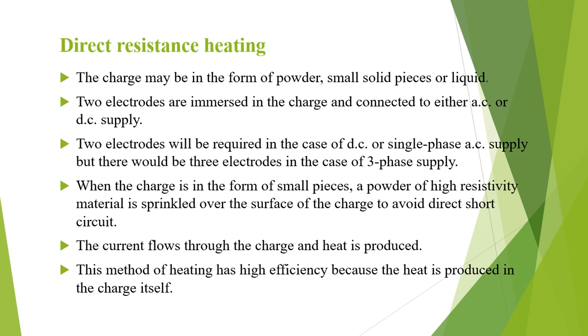The charge used may be in the form of powder, small solid pieces or liquid. The electrodes are immersed in the charge and connected to the supply — two electrodes are required for DC or single phase AC supply and three electrodes for three phase supply. When the charge is in the form of small pieces, powder of high resistivity material is sprinkled over the surface to avoid direct short circuit. The current flows through the charge and heat is produced. This method has high efficiency because the heat produced is in the charge itself.